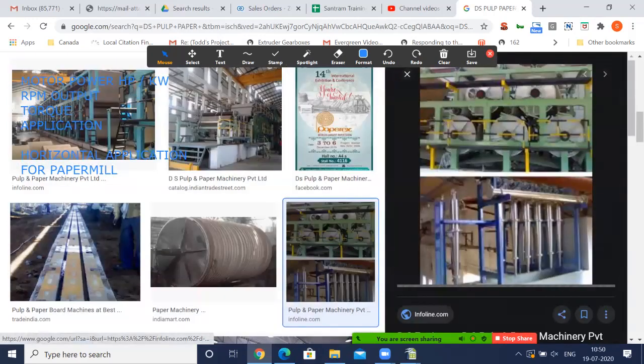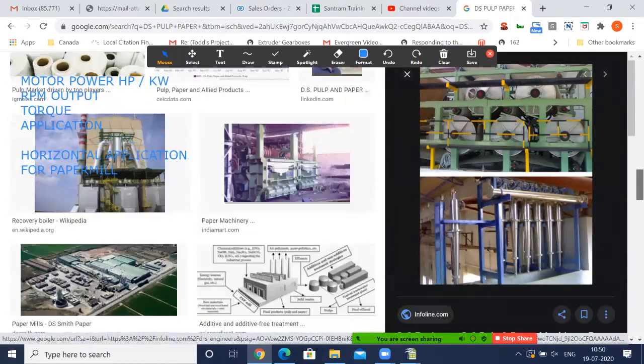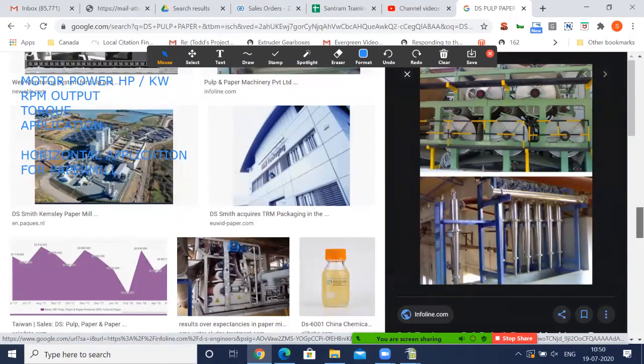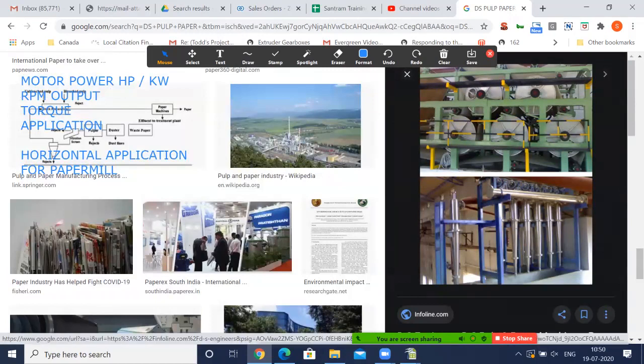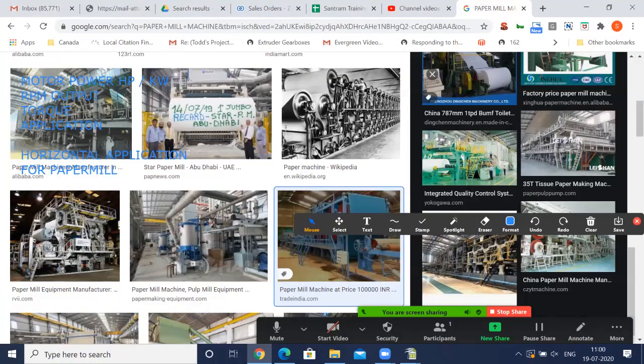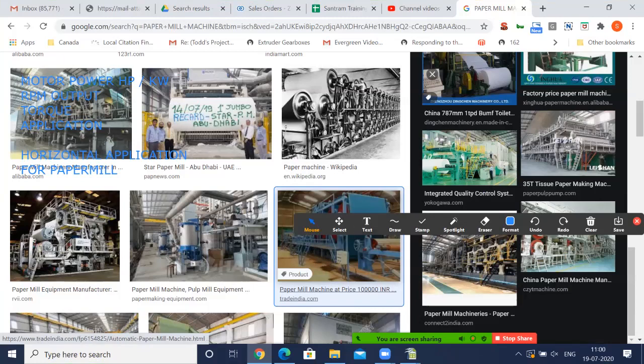See here the gearbox. Yeah, these rolls. So each roll on the other side is driven by a gearbox. So each gearbox is connected using a motor. Okay, so that motor itself, the sizing of the motor, the sizing of the gearbox is done model to model, and that is to be followed throughout each and every application. So all these rolls are rotated using those drives. So paper mills, these are the sectional drives, where almost 2 to 3 rolls have the same gearbox rotating them. Not like the whole mill runs on a single motor. They have individual motors, and that helps. That's the new way it works. That's called a sectional drive. It's not a line shaft. A line shaft is a single drive shaft which is connected throughout the paper mill. Okay, so that is not how it works nowadays.